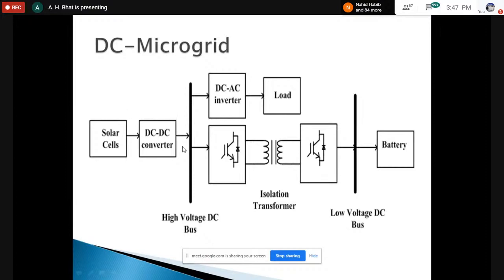So I repeat: under normal situations, when surplus energy is available, the load demand is fed by the high voltage DC bus, and simultaneously power flows from the high voltage DC bus to the low voltage DC bus, storing energy in the battery. When generation on this side reduces, power flows in the reverse direction since we already have energy stored in the battery. So power flows from the low voltage DC bus to the high voltage DC bus, and the load demand can be met from here.